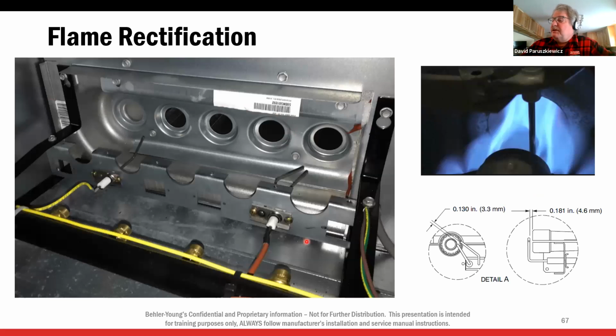So let's talk about flame rectification for a minute. This is the rooftop unit with the burners removed. Over here is our flame sensor with the pretty yellow wire. Again, that's not a thermocouple. Guys say, well, it's glowing cherry red. I don't care how hot it is. That's a conductor. We're carrying a low voltage current from the sensor through the flame to ground. That's how that works.